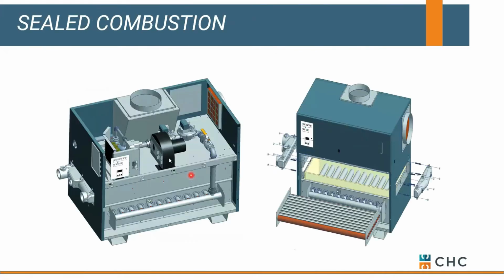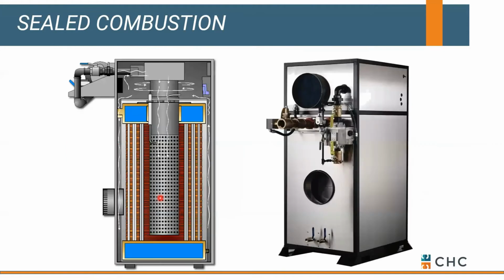So this is what a fan assist might look like. We're going to either pull combustion air in from the mechanical room, or it could be ducted from the outside, and bring that into our fan, where it grabs the air and sends it into our combustion chamber, where this is with gas. We have spark down here, and we have heat transfer. Okay, so that's a good example of a horizontal boiler setup. You can also go vertical with the same configuration. Again, this is our air inlet. This is our vent, where flue products leave the boiler and head outside. Kind of looks like a big fridge, but just to save floor space.